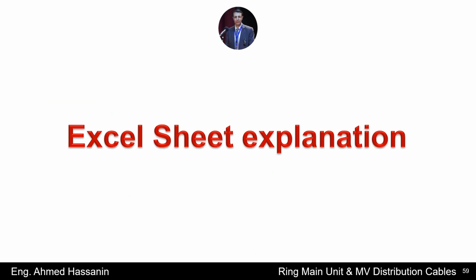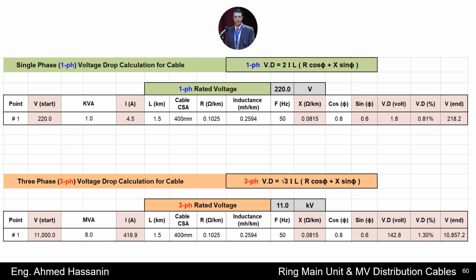I made an Excel sheet that has all the previous voltage drop calculations, and in a very easy way, anyone can deal with these tables and change any data according to their project. In the first table, I will explain how to use this table to make the voltage drop calculations for any single phase load for any cable. In the second table, I will explain how to use this second table to make the voltage drop calculations for the three phase load for any cable.